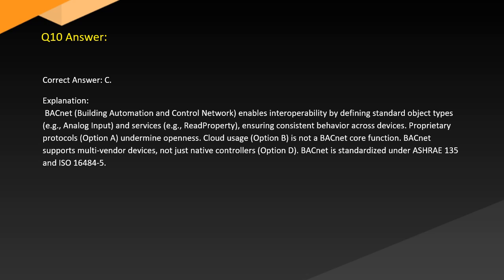Answer. Correct answer: C. Explanation. BACnet, the building automation and control network, enables interoperability by defining standard object types, e.g. analog input, and services, e.g. read property, ensuring consistent behavior across devices. Proprietary protocols, option A, undermine openness. Cloud usage, option B, is not a BACnet core function. BACnet supports multi-vendor devices, not just native controllers, option D. BACnet is standardized under ASHRAE 135 and ISO 16484-5.